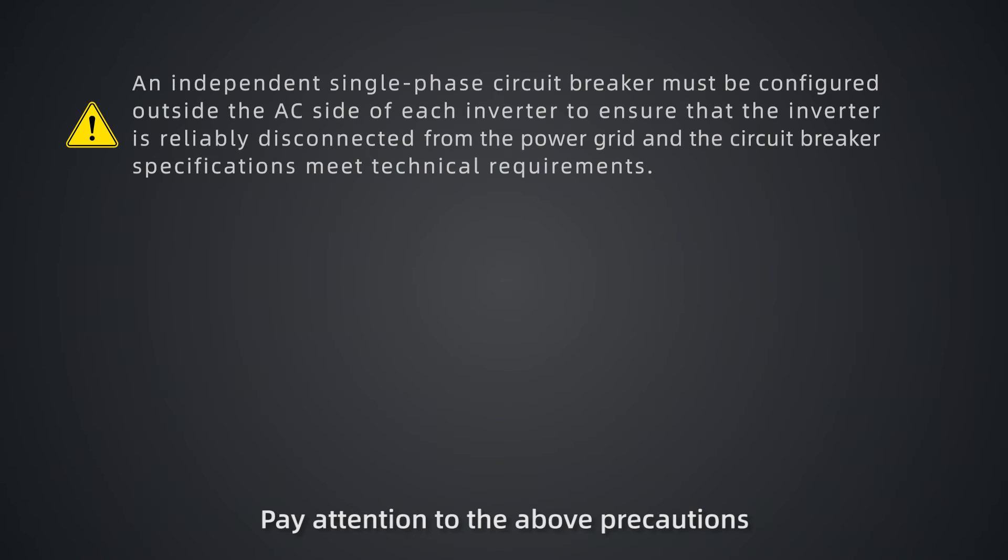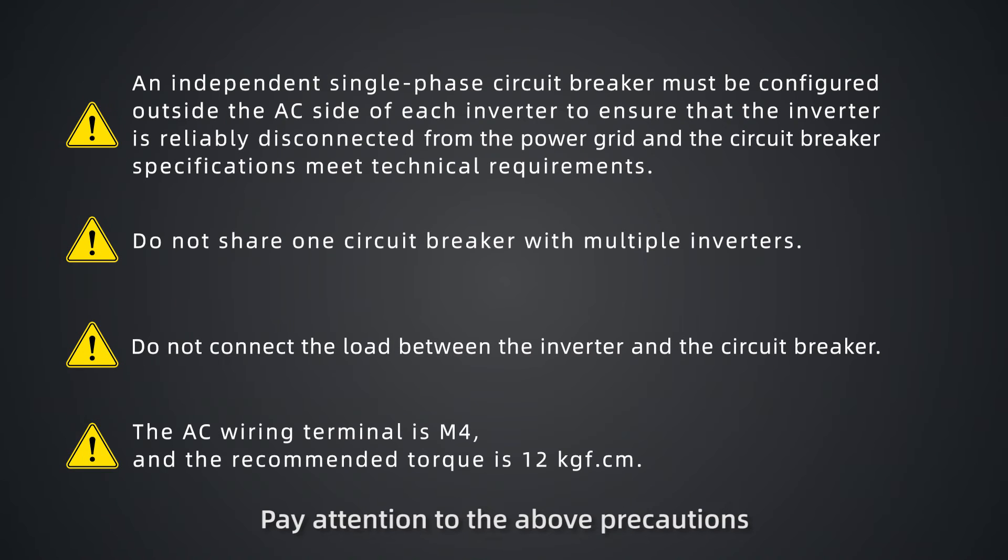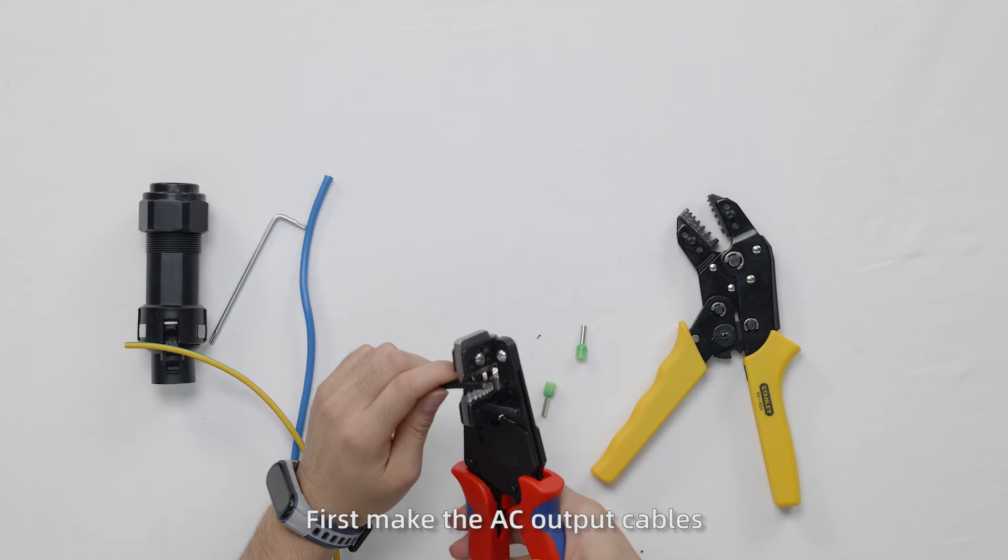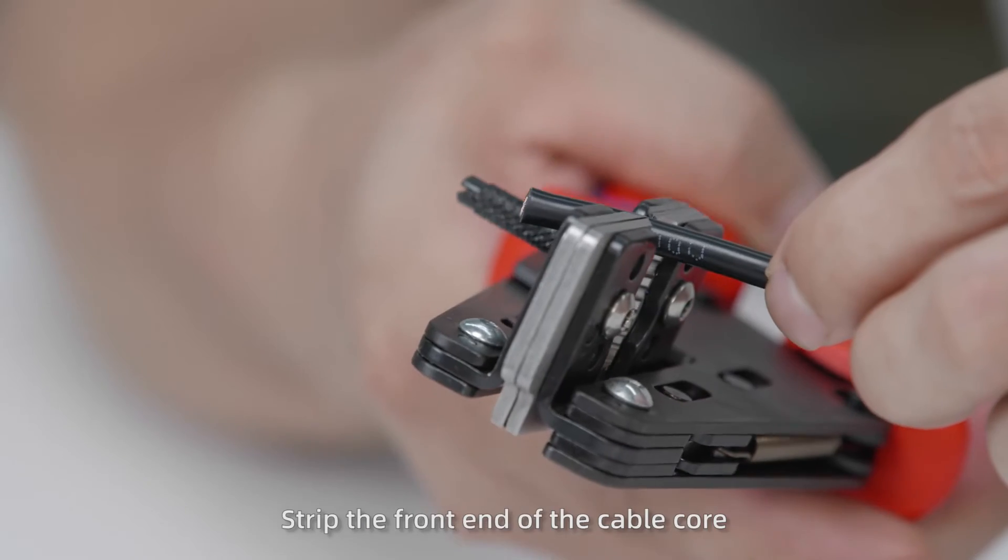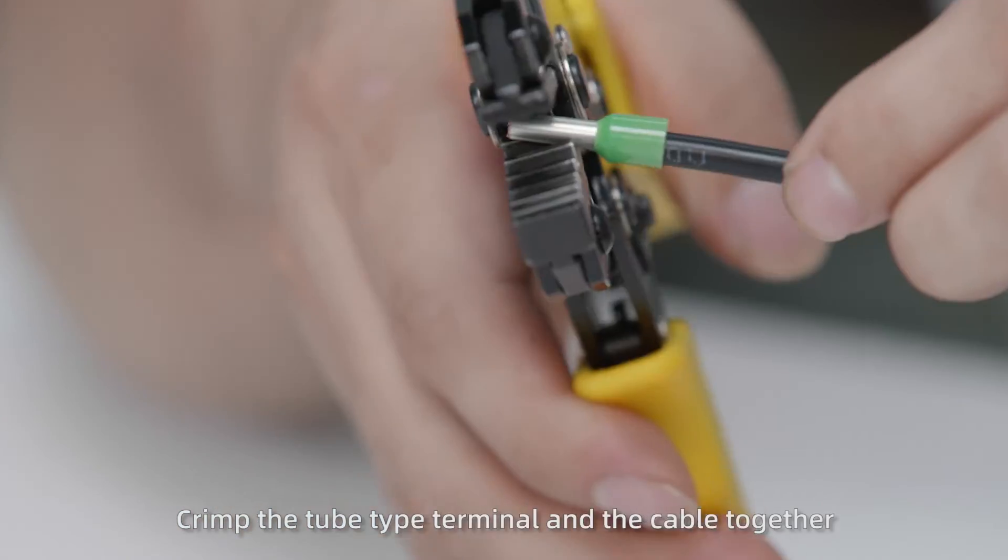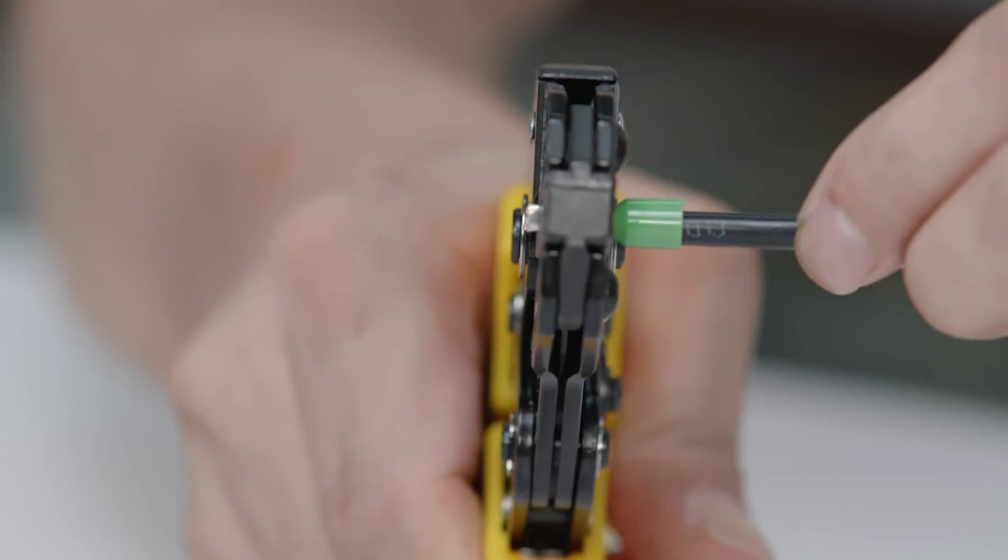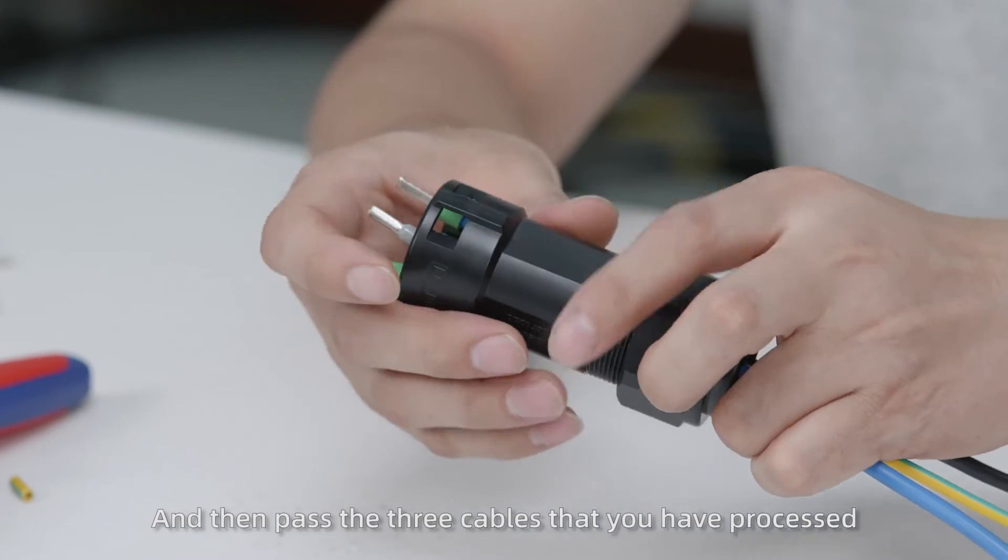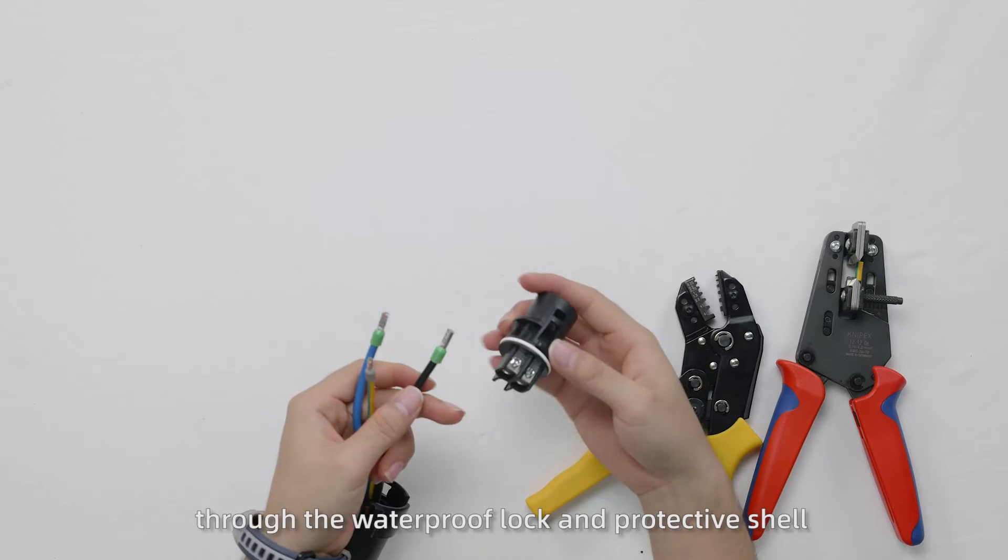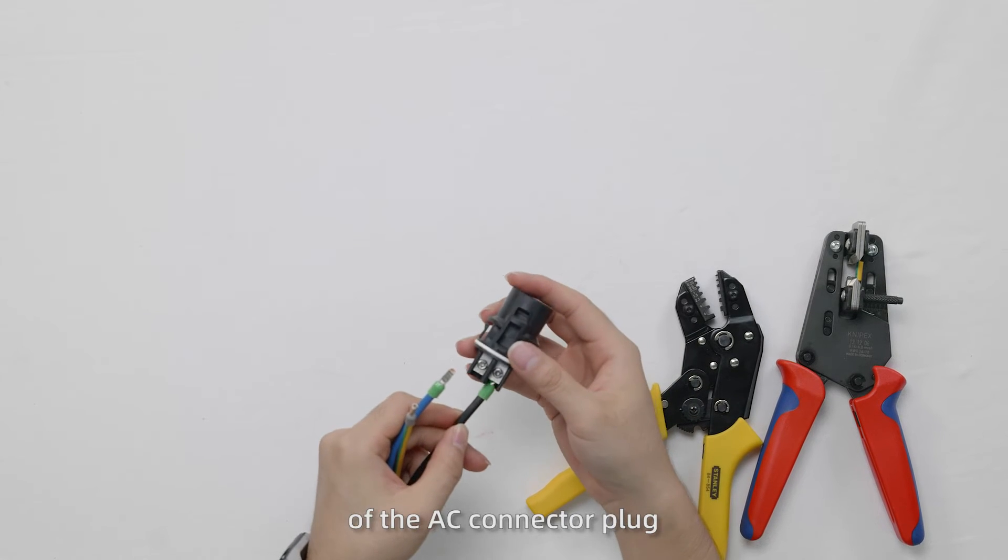Then, connect cables on the AC side. Pay attention to the precautions before cable connection on the AC side. First make the AC output cables. Strip the front end of the cable core, crimp the tube type terminal and the cable together. Then pass the three cables through the waterproof lock and protective shell of the AC connector plug.